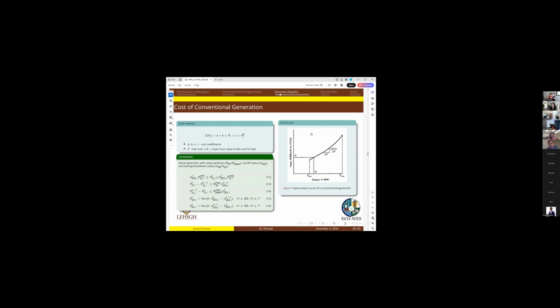And here you can see the cost curve. First of all, each unit is going to have a minimum and maximum power. That means, for example, if you have a 6 megawatt combined heat and power generation, its maximum power is 6 megawatts and its minimum power is 0. So it's going to give you something between 0 and 6 megawatts.